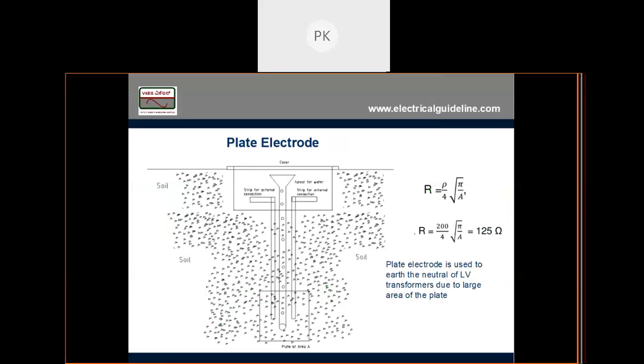Okay, then I will tell you why plate earthing is used for the neutral. Even in the case of a common grid, the transformer neutral and body earthing experience the same potential as the lightning stroke that is applied on the structure. If lightning strikes the transformer, the first thing is there is lightning protection. Even after that, if it strikes the structure, then the potential rises. Finally, it is the earth grid where the potential will rise, because the lightning current finally enters the earth grid.